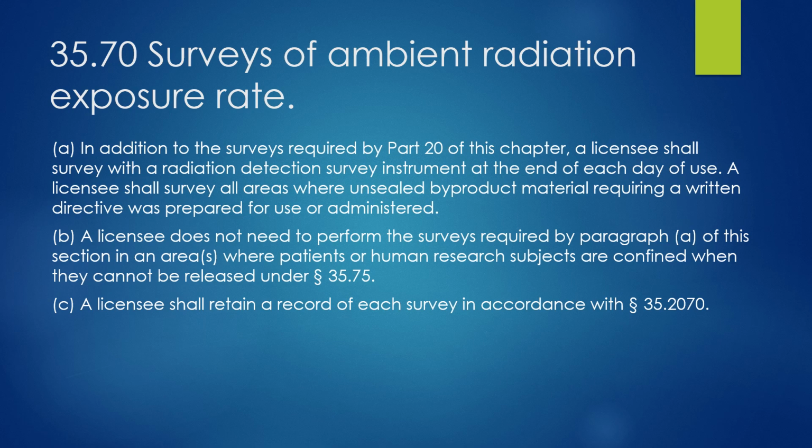But when you break down that room, you would have to survey it and decontaminate it and everything, but you wouldn't have to go in there every day. But to every other area where any radioactive material was used or stored, you need to do your daily surveys and then keep those records for 3 years.